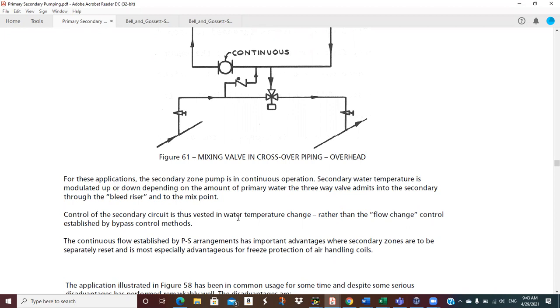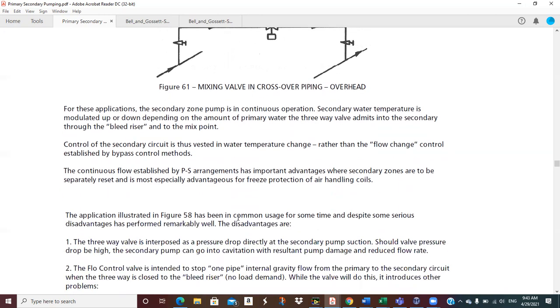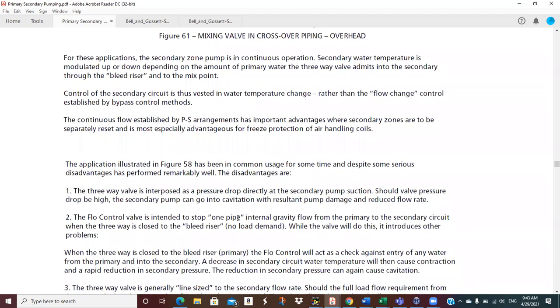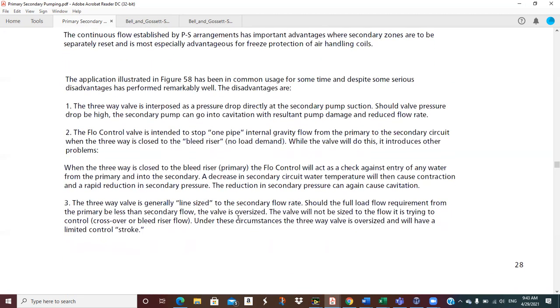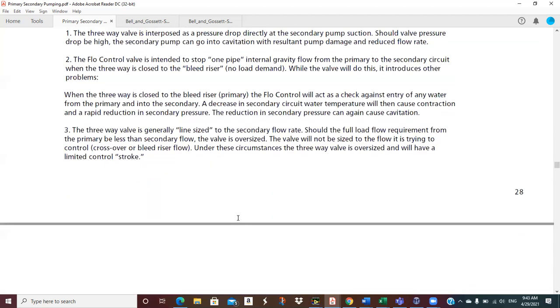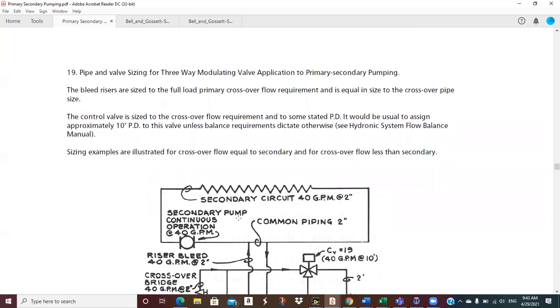It's a trade-off. The continuous flow established by primary secondary arrangements has important advantages where secondary zones are to be separately reset. And so, you know, with those three-way valves, you can reset that water temperature with outside air or with anything you want to. And of course, it also provides freeze protection because we're pumping the coils continuously. I think we've done enough of that. That was fine. So yeah, you can read through those, but I think I pretty well talked through that.